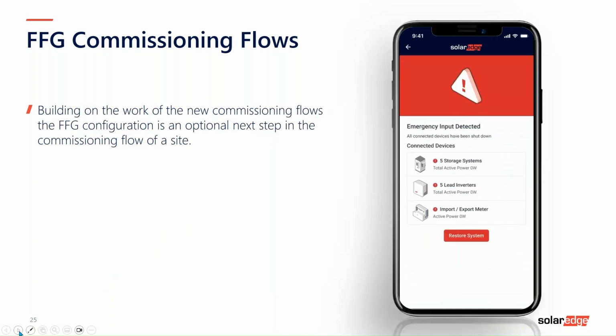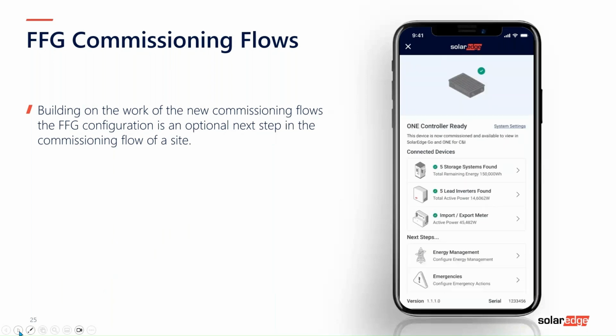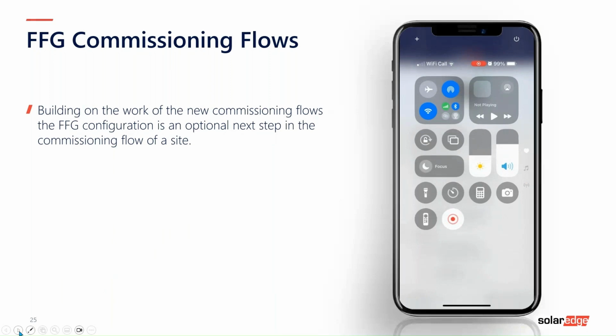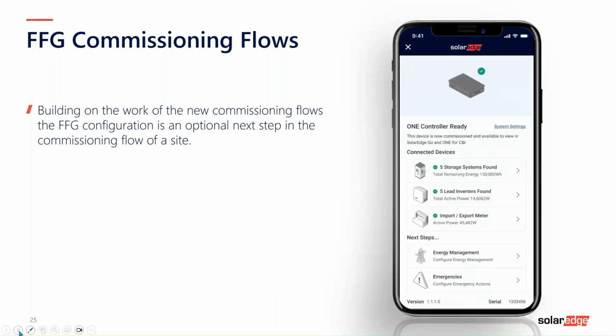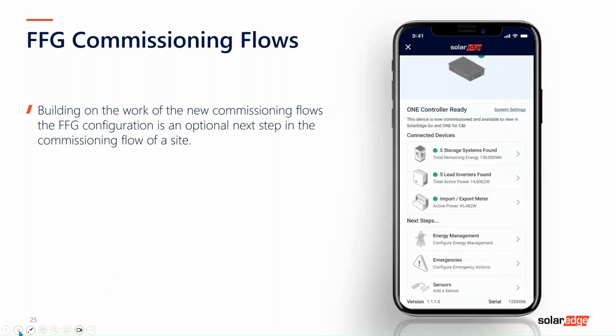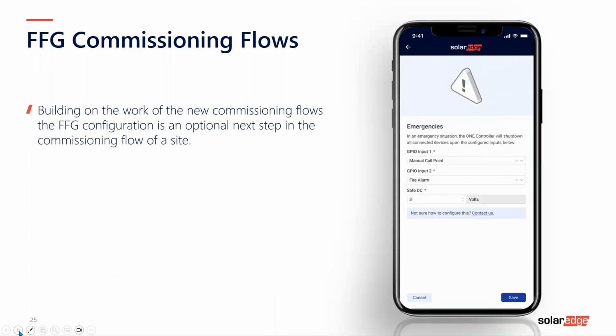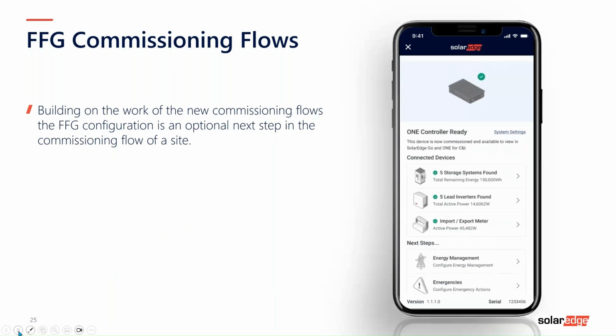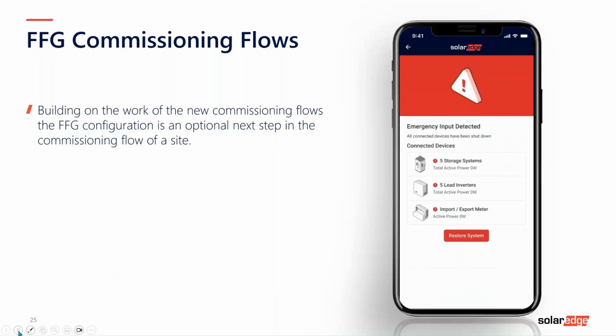This is basically saying the emergency has been detected. The Firefighter Gateway feature is activated on the inverter, and you can restore the system without going to site. So should it be a false alarm, or should someone have knocked an emergency stop and they don't know what to do, instruct them to release the emergency stop, and you can reset the system.